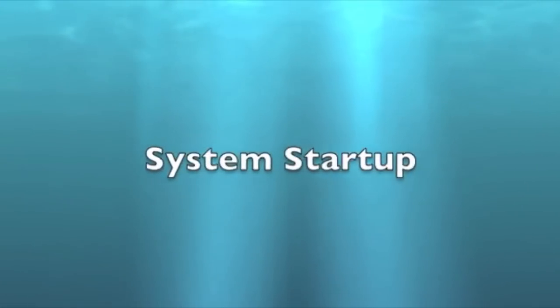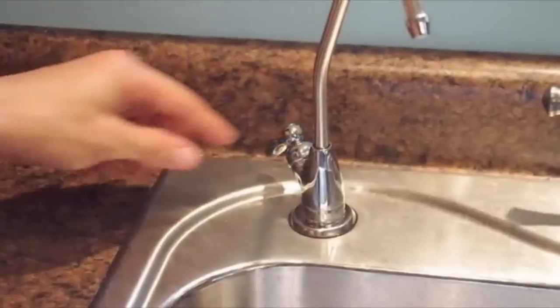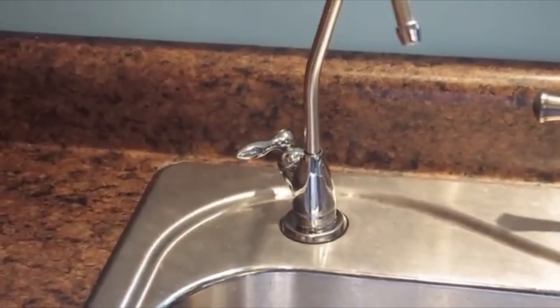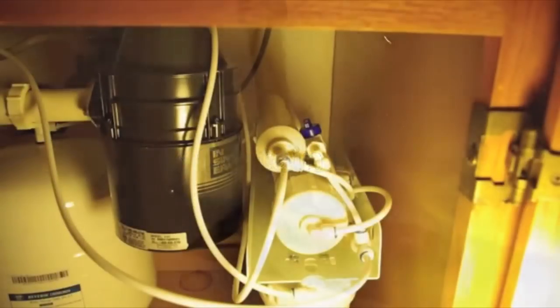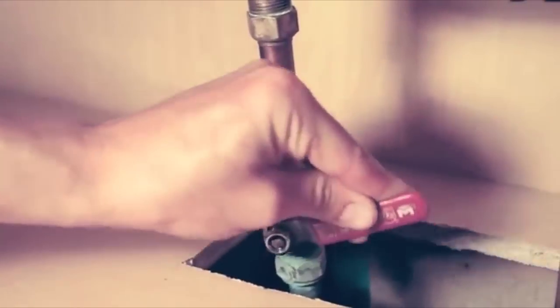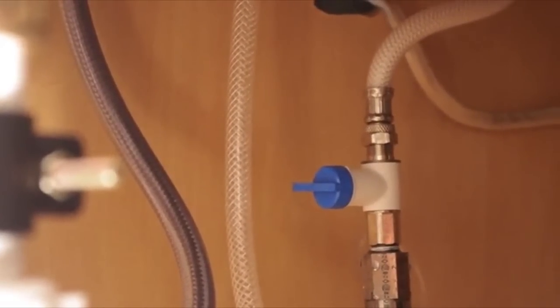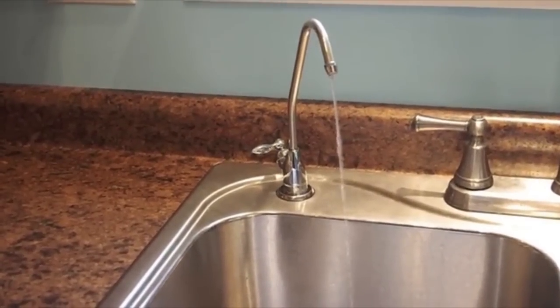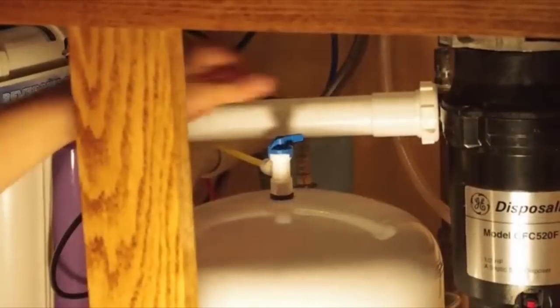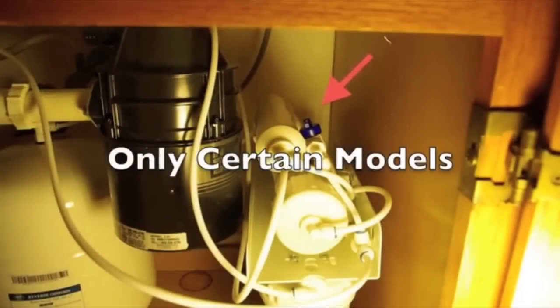System startup. Turn off the tank valve so the handle is perpendicular to the hose. Turn on the reverse osmosis faucet. In systems with manual flush valves, open the flush valve. Turn on the cold water supply. Turn on the reverse osmosis supply valve and check the system for leaks. After five minutes, water should start to dribble from the faucet. Turn off the manual flush valve if installed.